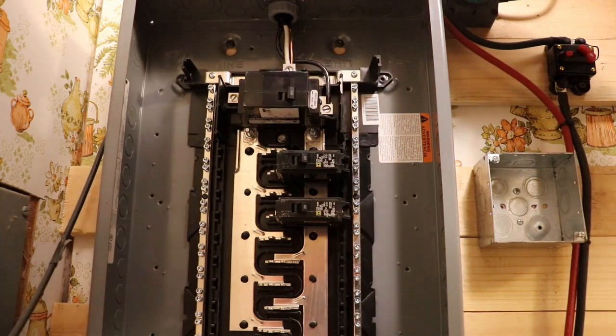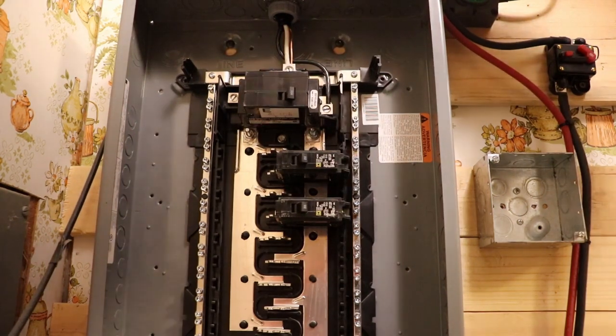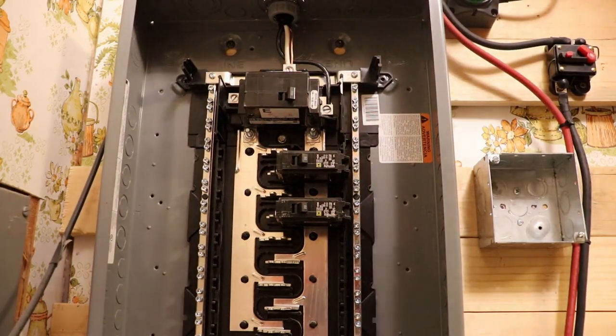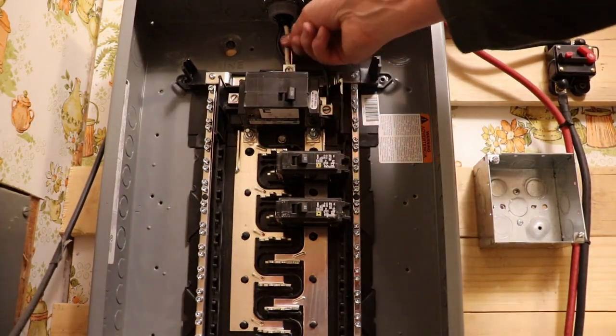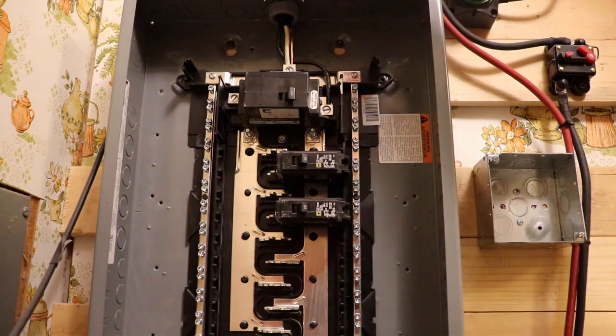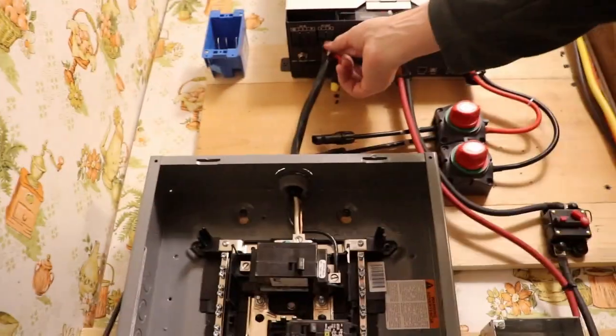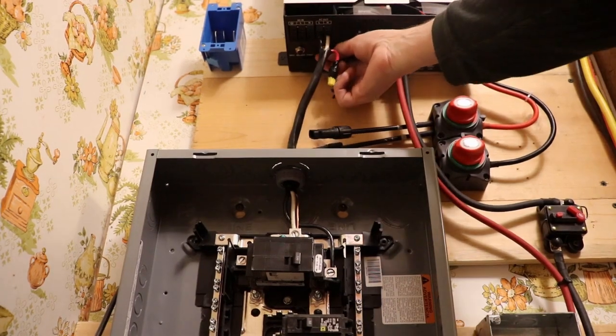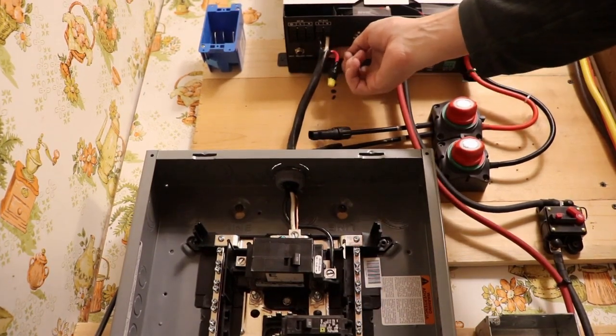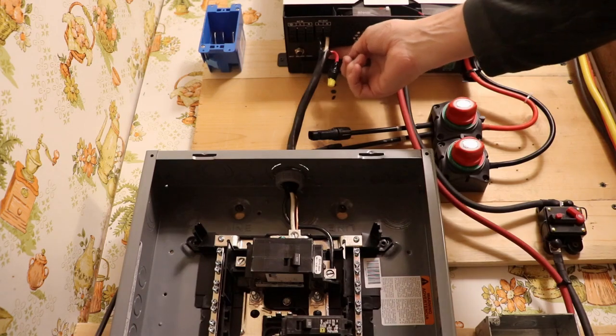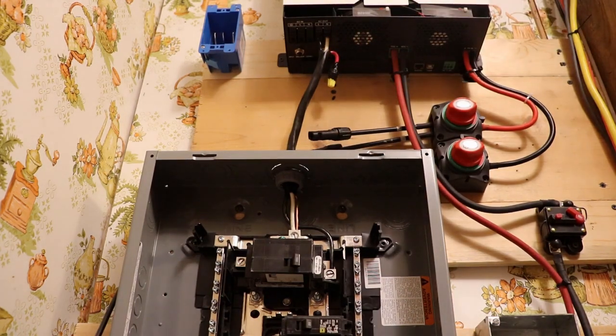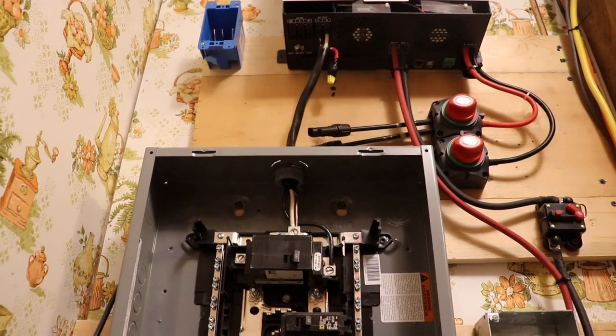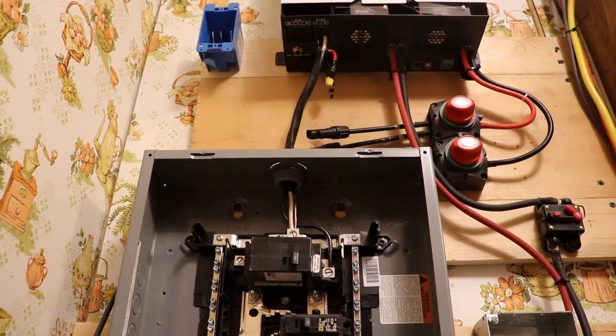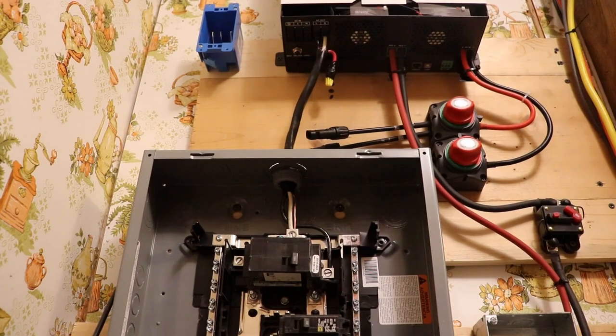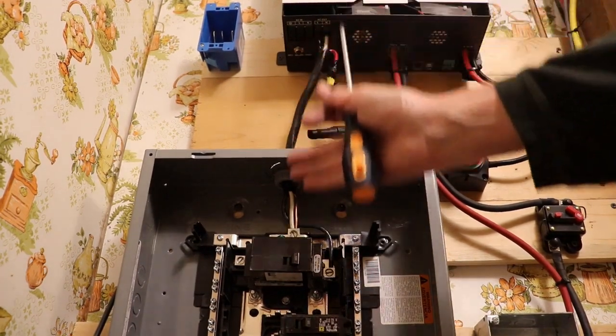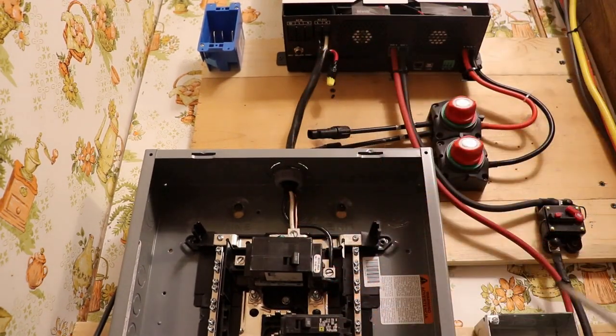The basic idea is for this to hold the wire. It's holding the wire, and that's what I want. I want to make sure I pull on these and can't pull them out. Same thing with the top up here—make sure you can't pull these wires out. Make sure you have a good ground, and that the ground is underneath that washer, so you've got a good ground on that wire. You want everything good there. So that's going to be the 120 coming into this panel box.